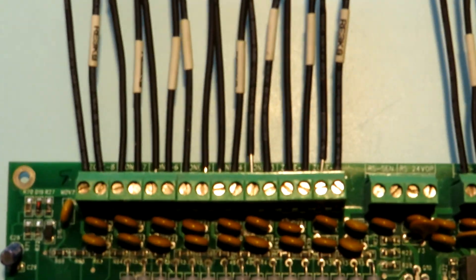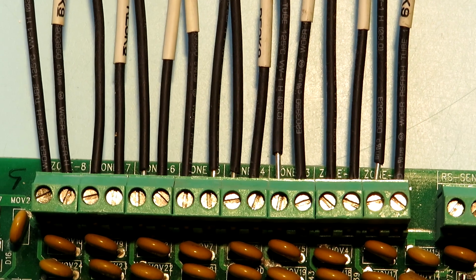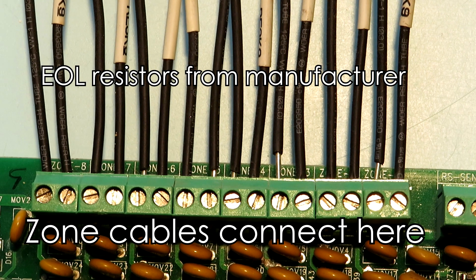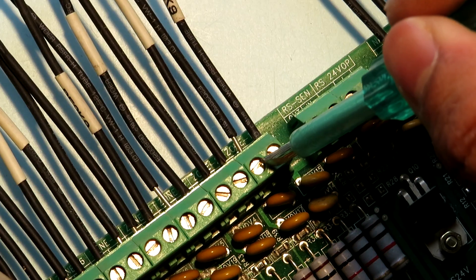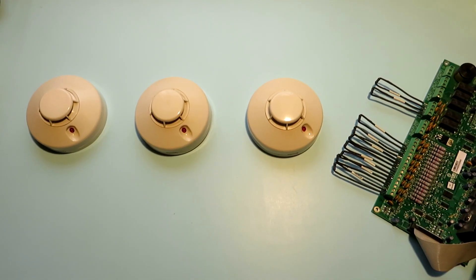This is an 8 zone panel and the wires from the 8 zones connect here. The black things you can see on the top are EOL resistors that have been provided by the manufacturer. Here I'll be connecting the detectors to zone 1. So I'll take out the EOL resistor and insert the zone cables.